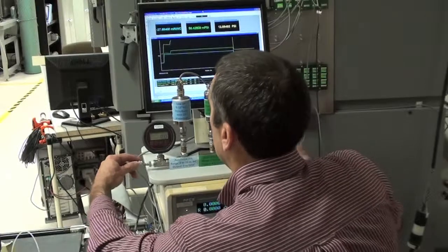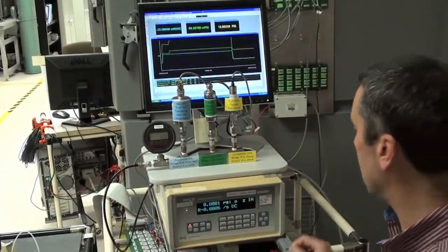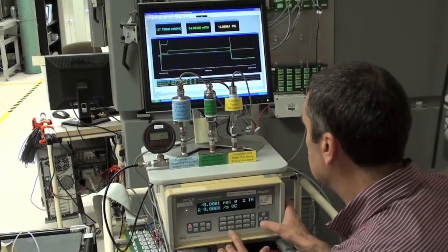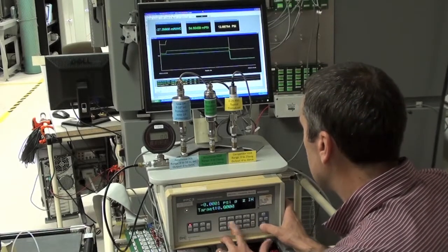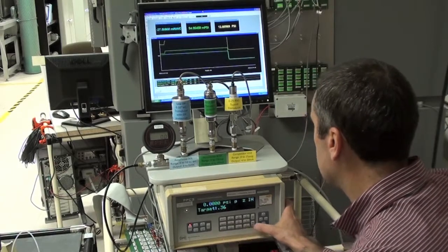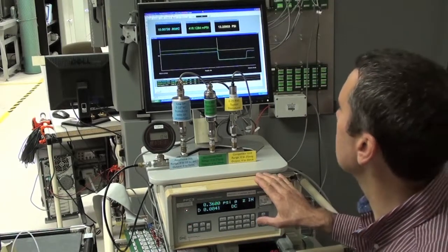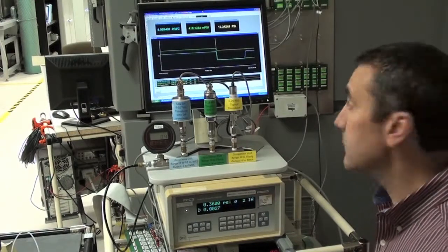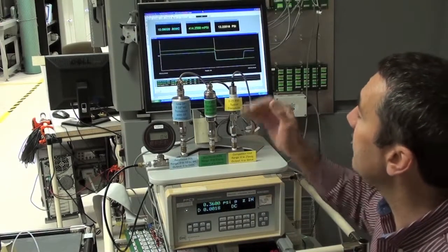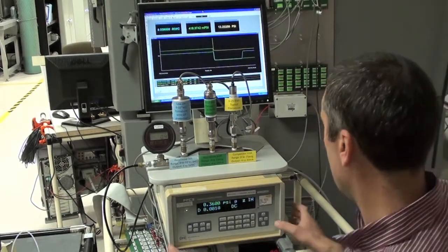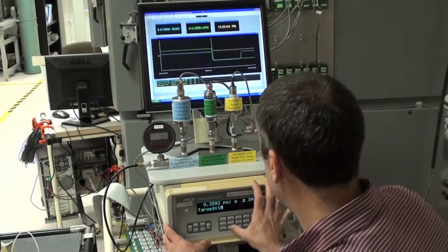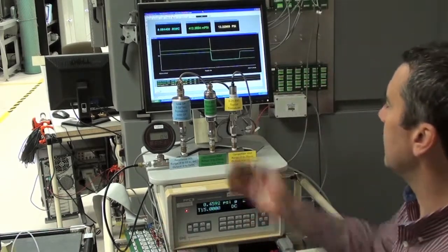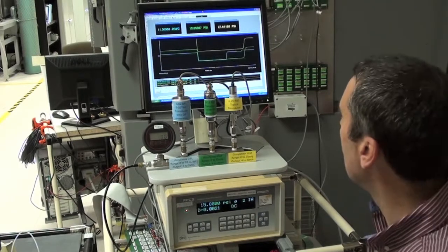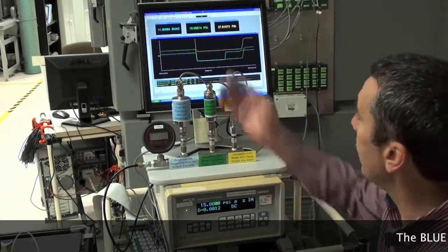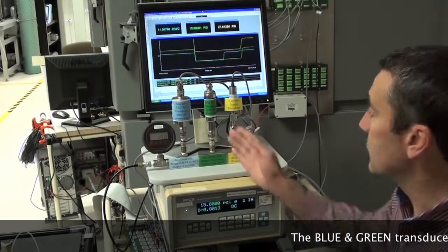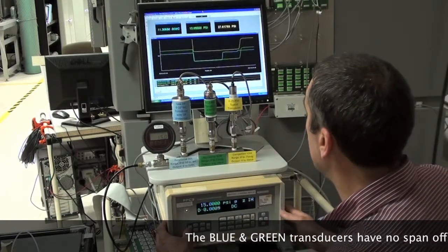So let's check what happens when we apply the full-scale pressure. Let's start with the 10 inches, which is 0.36. So it's pretty close now. As you can see, 10 inches of water, pretty spot on after having received over 500 times its full-scale pressure. Now let's apply 15 psi. See what happens to the other transducer. And there it is. It reached 15 psi. It's reporting 15 psi.